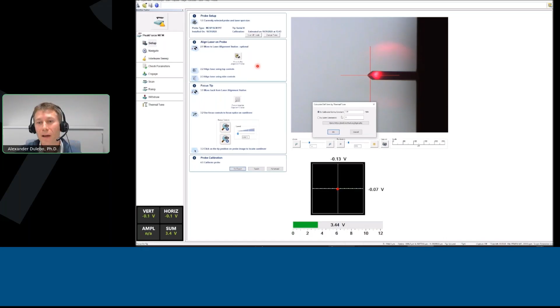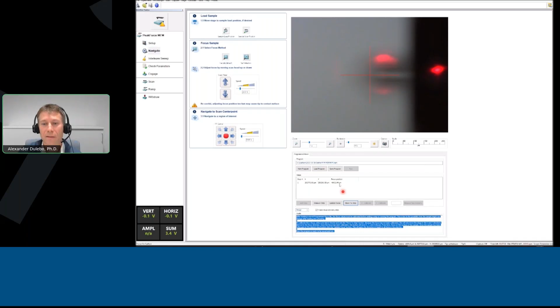So I can do a quick probe calibration using touchless calibration here and get the deflection sensitivity, which is quite nice and convenient. So again, my position is already defined, so I found a nice spot on this hard disk drive. So using the program move, I can go directly there and to the right position with the accuracy of the motorized stage.